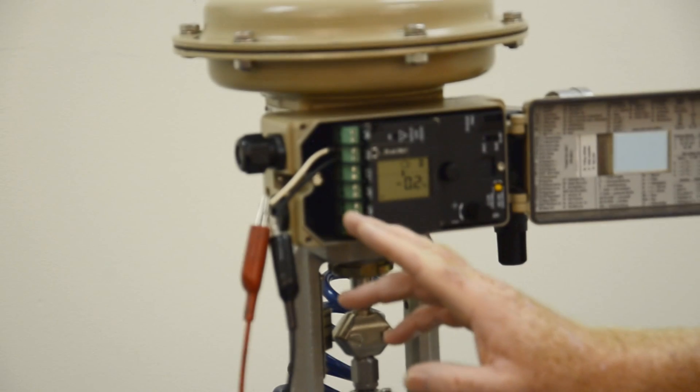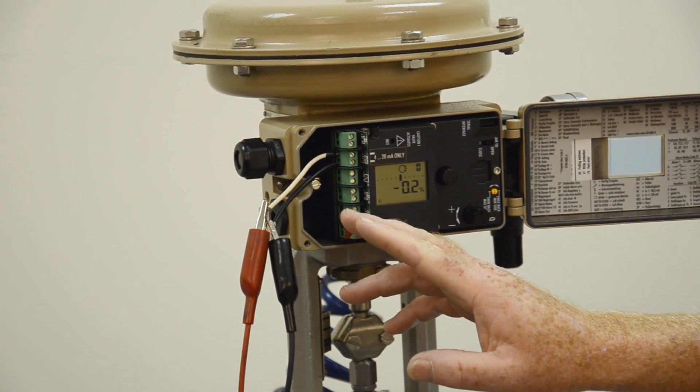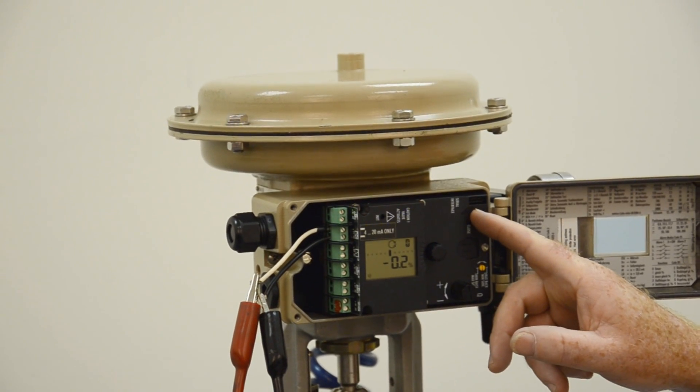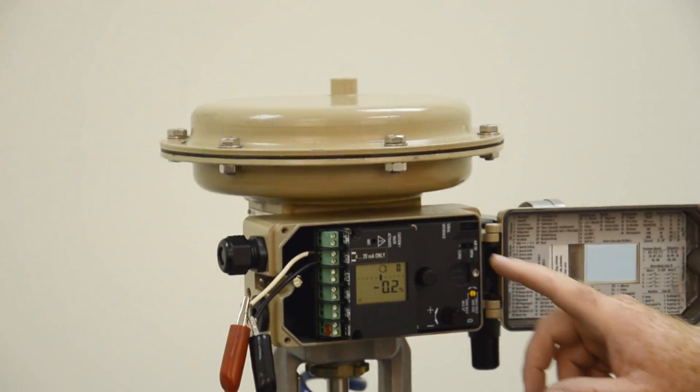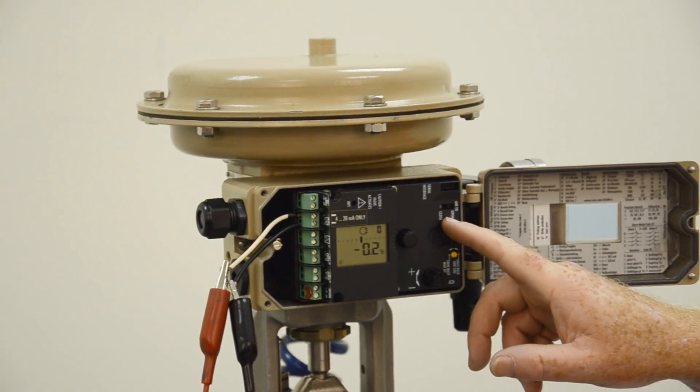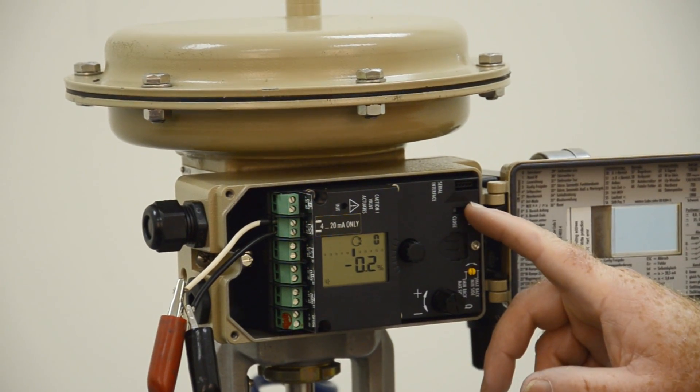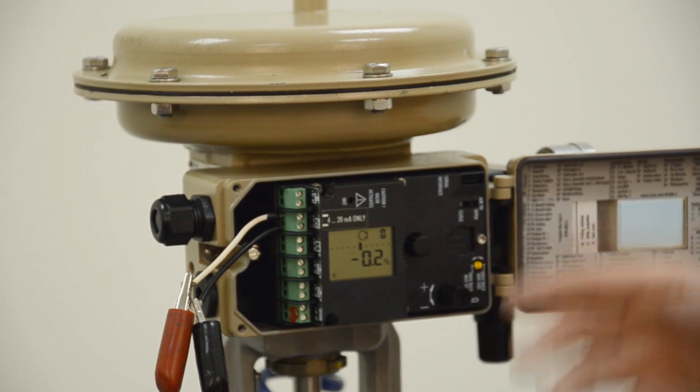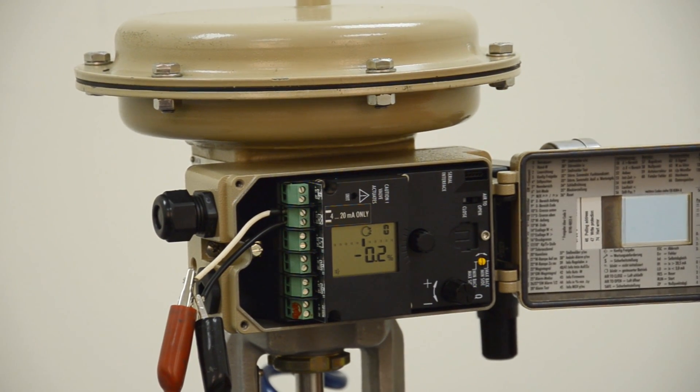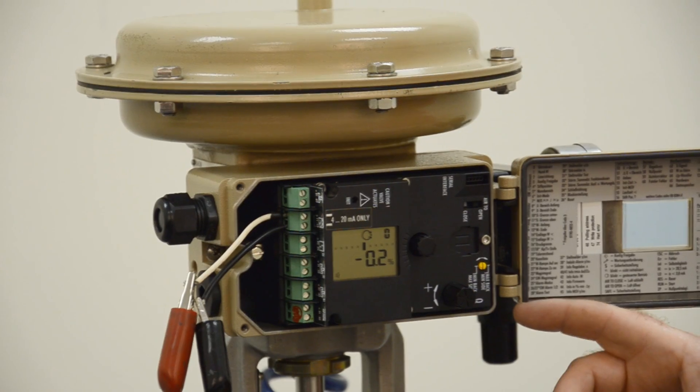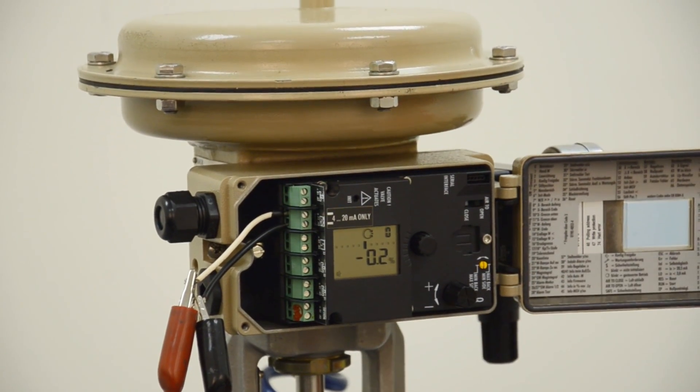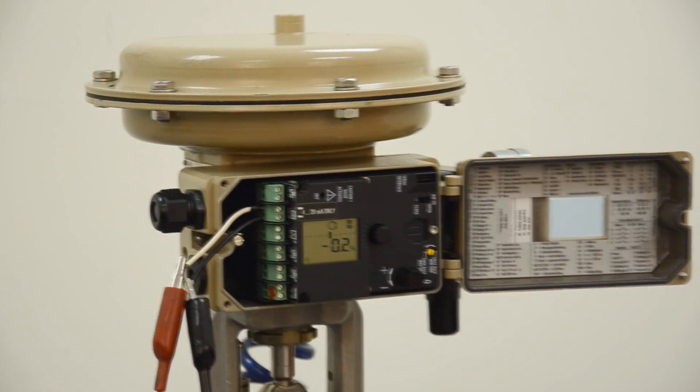And this can be done through what we call a rotary push button. First off, on the positioner, you will see your terminal board, your display. There's a serial interface connection. There is an air to open or air to close switch, which you will need to move to the proper position based on your failed position of your valve. Once you've done that, then you are ready to start configuration.